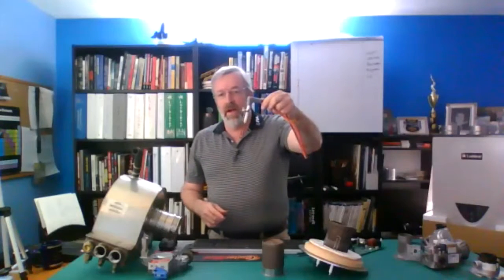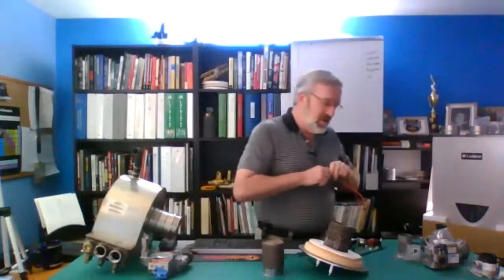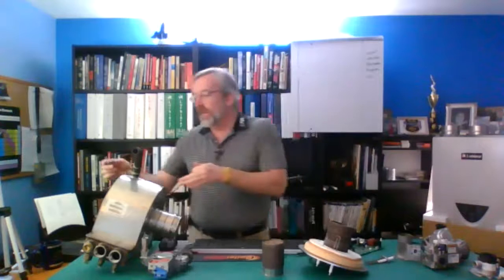If I don't spark here, really step 2, take the spark electrode off, take your cable, and hold your cable over near one of the studs on the heat exchanger. Now don't put it on there, but just hold it off, let it spark across that distance, that spacing there, and see it spark on there. If I spark here, I'm gonna wanna look at this.